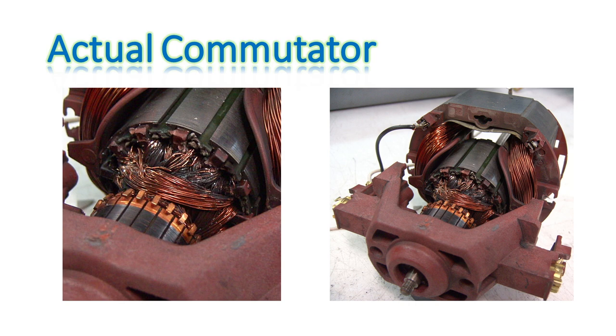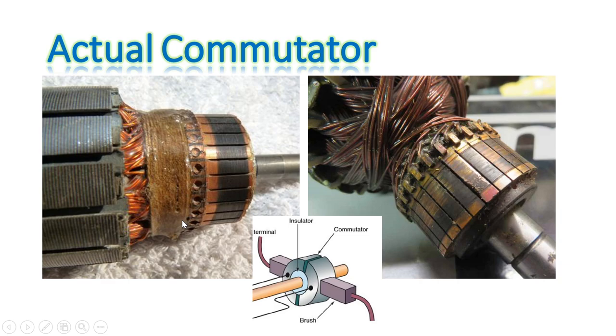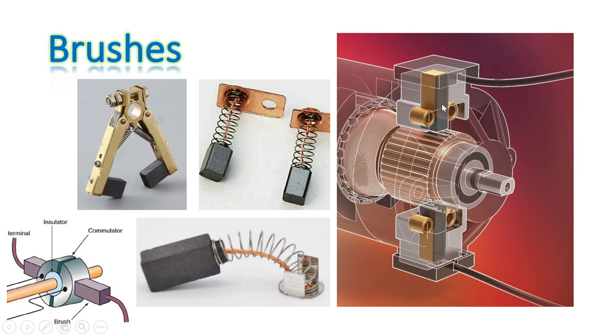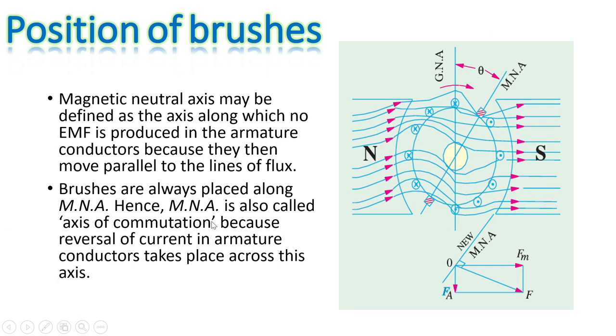Obviously, the actual commutator is not that simple — it has many segments and is not just a two-segment split ring. The actual machine has many small segments in the commutator and many coils. There are many windings, each connected with a separate commutator segment. To collect current from this rotating commutator, we have a brush assembly. These brushes are housed inside a proper mechanism which continuously presses them through a spring, and the brushes are made of carbon.